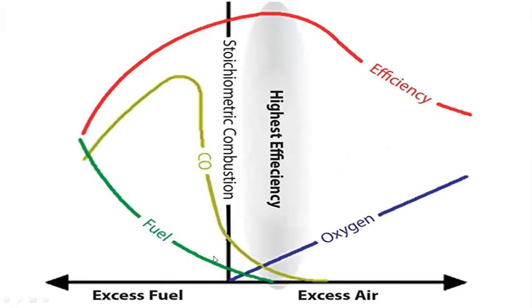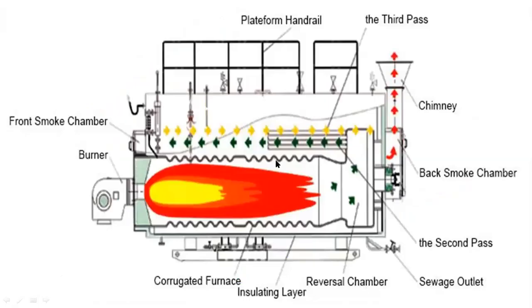The stoichiometric combustion requirement states C + O2 → CO2: for every 12 grams of carbon, you require 32 grams of oxygen O2 to give 44 grams of CO2. Beyond that, you need to give some excess air for proper combustion. You will see that efficiency is highest at around 4% oxygen in the flue gases, with minimum carbon monoxide and around 13% carbon dioxide. So around 4% oxygen is the most appropriate level for high-efficiency combustion when we take combustion efficiency into account.